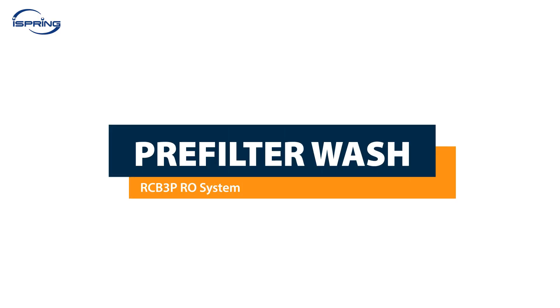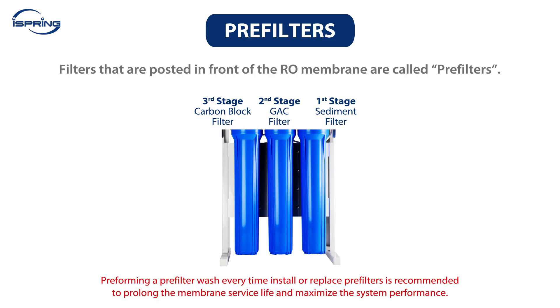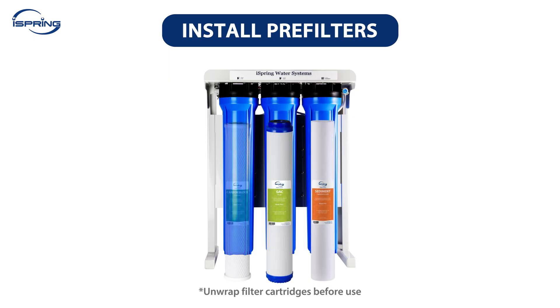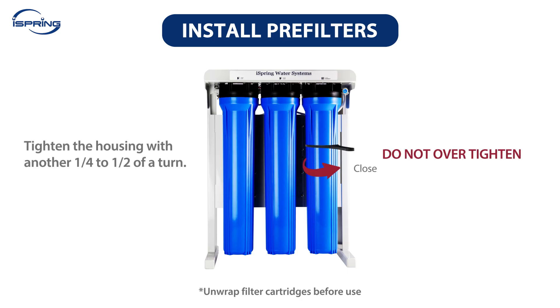Pre-filter Wash. Filters positioned in front of the reverse osmosis membrane are called pre-filters. We recommend performing a pre-filter wash every time you install or replace pre-filters to prolong the RO membrane service life and maximize system performance. Step 1: Unscrew Stage 1, 2 and 3 filter housings. Take out and unwrap all the filters. Step 2: Insert the filters back into their housing and ensure the housing O-rings are properly seated to prevent leaks. Step 3: Twist the housing clockwise onto the housing caps. Using the housing wrench, tighten the housing another quarter to half of a turn. Do not over-tighten as this can cause leaks and make future filter replacement difficult.